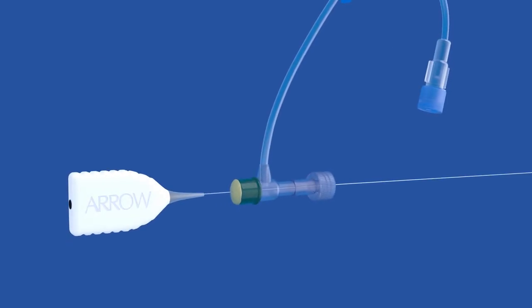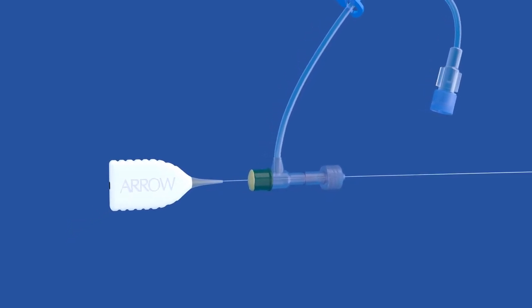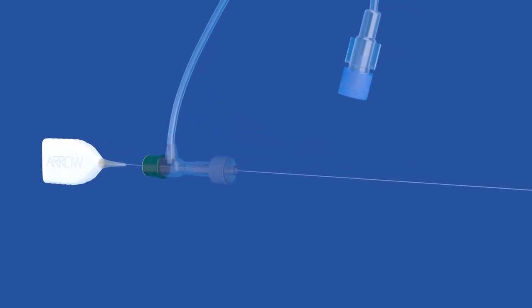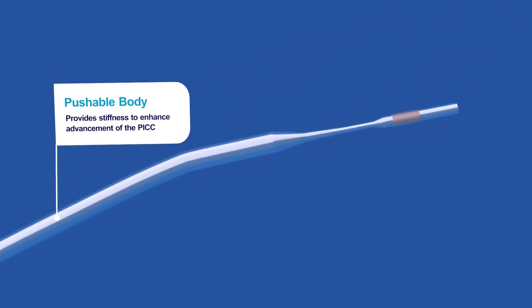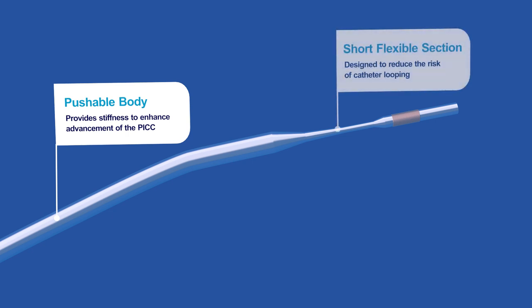In addition to being a component that enables tip location and navigation, the Arrow NaviCurve Stylet has other design features that make it easy to advance the PICC into the SVC on the first attempt. An anatomical curve allows the NaviCurve Stylet to self-orient to the human anatomy. The pushable body provides stiffness to enhance advancement of the PICC, while the shorter, flexible section of the stylet tip is designed to reduce the risk of catheter looping.